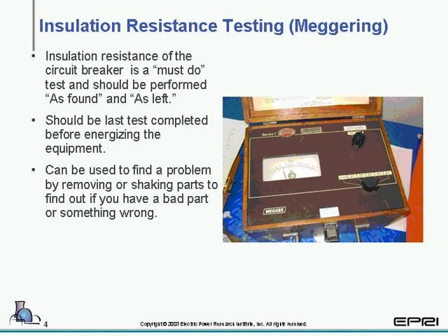We have several slides that we're going to take a look at on meggering. Insulation resistance of circuit breakers is a must-do test and should be performed as found and as left. And one of the items that we're going to talk about in the very last sentence is shaking the parts. What we're trying to get at, especially with the arc chutes, on certain design pieces of equipment, you can actually move the arc chute around and watch the insulation value change.